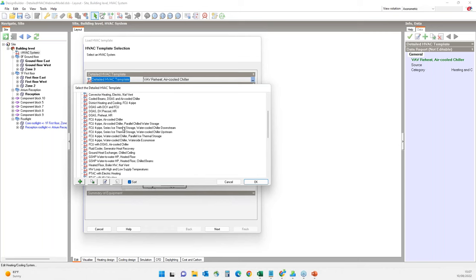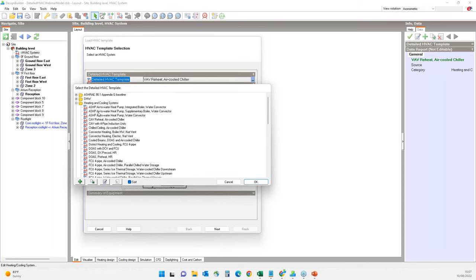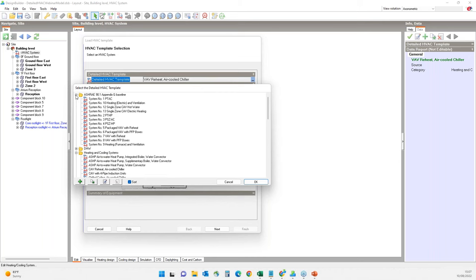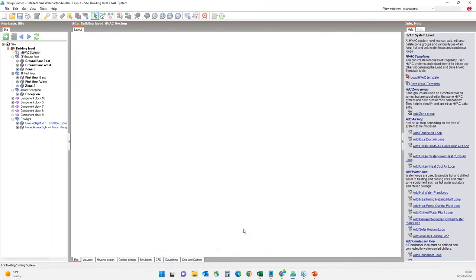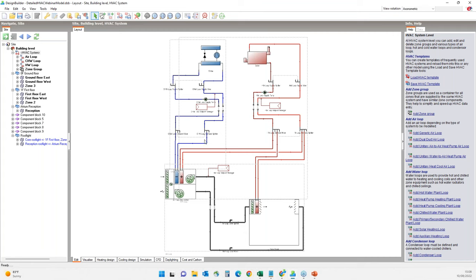The simplest way to start with detailed HVAC modeling is to load an existing HVAC system using the templates. Design Builder has lots of pre-configured detailed HVAC templates. There are also templates for ASHRAE 90.1 systems, typically used during LEED ASHRAE 90.1 baseline modeling. For this part of the webinar I will start with the VAV reheat air-cooled chiller template, adding it to all zones. This system has four components: air loop, chilled water loop, hot water loop, and the zone group.